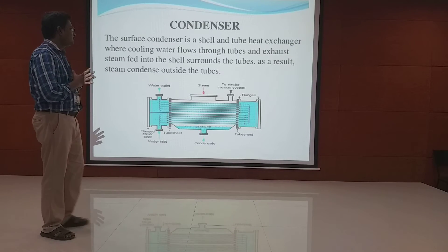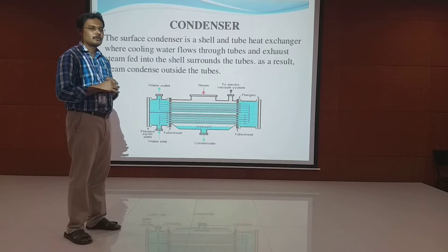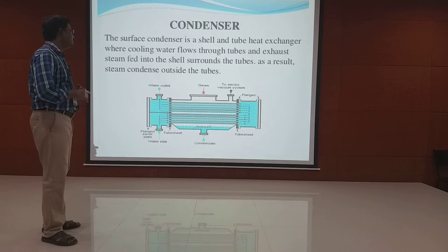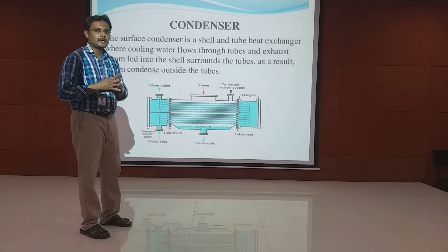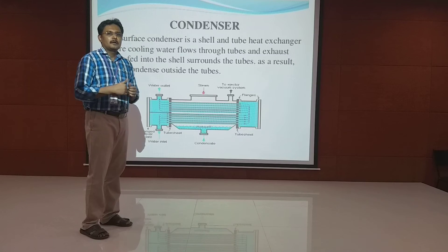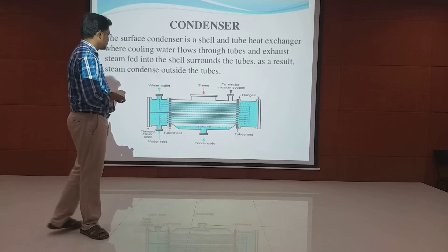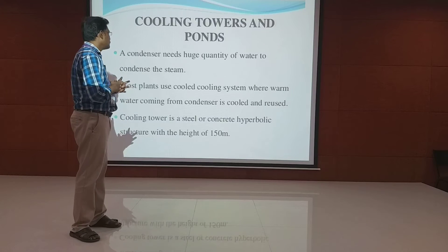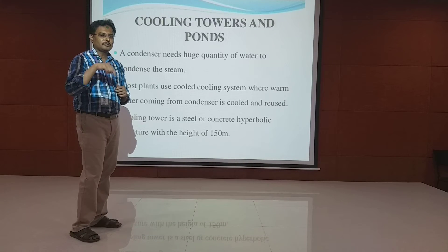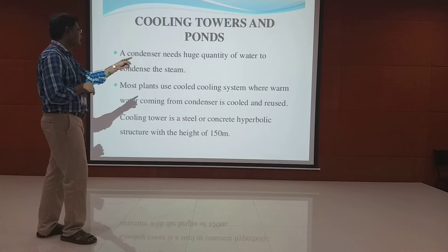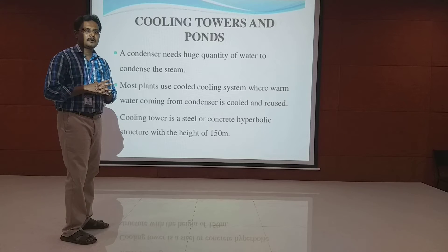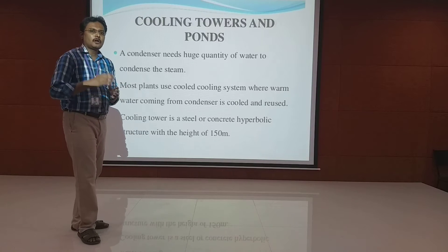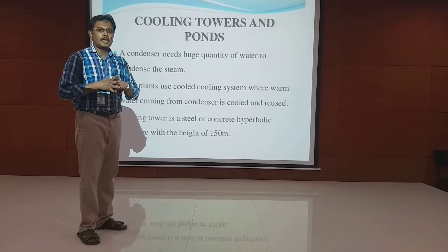A surface condenser is used as a heat exchanger, where cooling water flows through horizontal tubes placed inside the condenser, and exhaust steam fed to the shell surrounds the tubes. As a result, the steam condenses outside the tubes. The cooling tower aids the condenser, which needs a huge amount of water to condense the steam completely. Most plants use a closed cooling system where warm water from the condenser is cooled and reused. The cooling tower can be made of steel or concrete at a height of up to 150 meters.